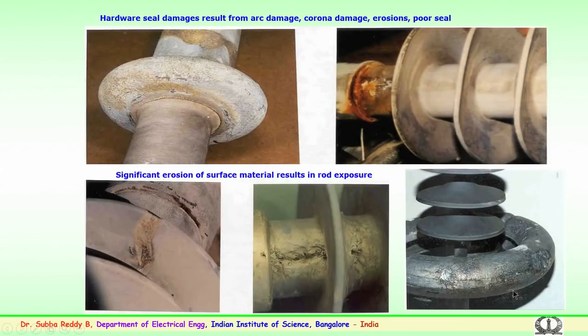There are further reports about hardware damages. You can see here the corona control ring or the end fitting which is fixed to the insulator surface degraded over a period and becomes highly corrosive, and this leads to the failure of the insulators over a period of time. You can see again these failures of the corona ring due to lightning surges or over a period of time in service, where failures have been noticed. Again here it is tracking or surface erosion which has happened in both the cases. This could result in the failure of the rod exposure.